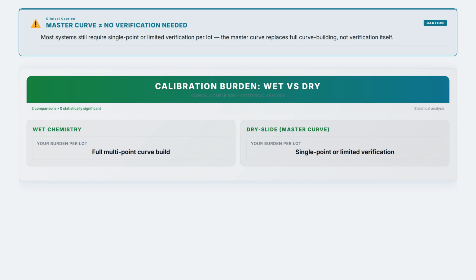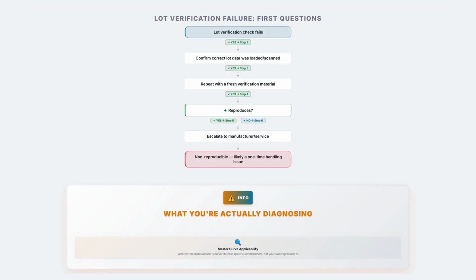If that lot verification check fails, the troubleshooting logic runs differently than the shift or rotation or outlier taxonomy from the wet chemistry calibration discussion. Because you're not diagnosing your own regression fit, you're diagnosing whether the manufacturer's master curve genuinely applies to your specific slide lot and instrument, or whether something in your local storage, handling, or instrument condition has shifted.